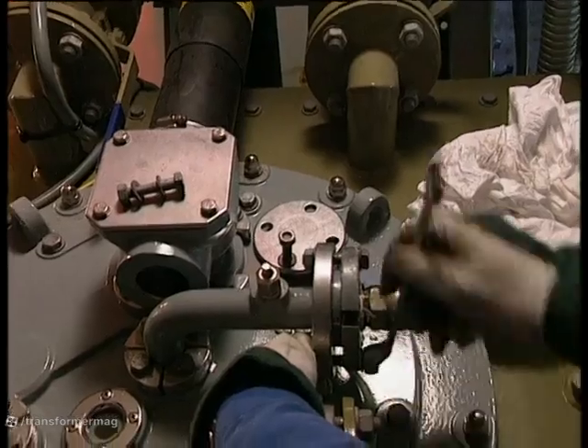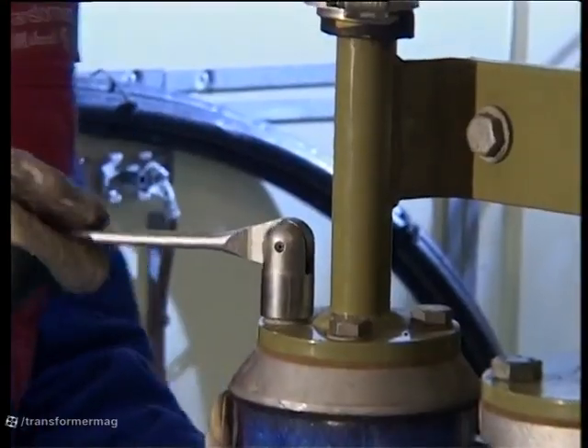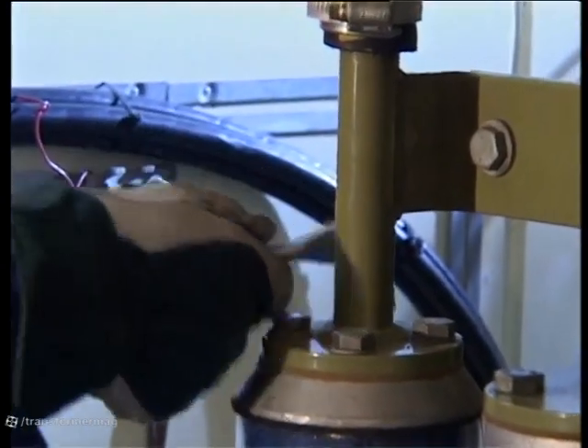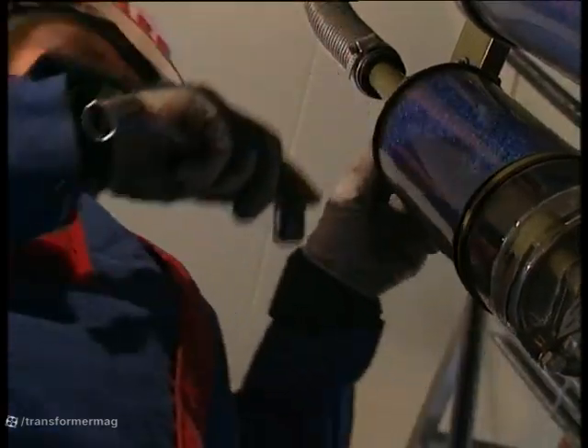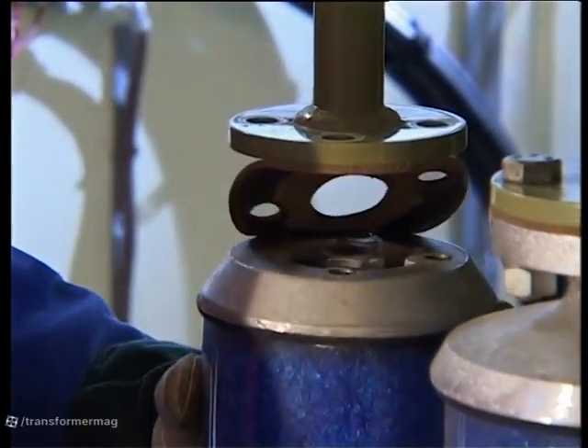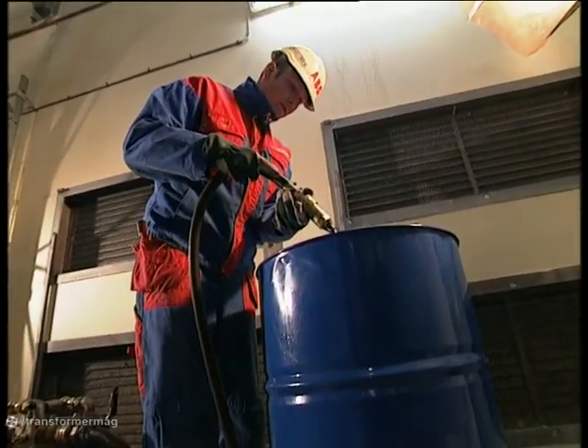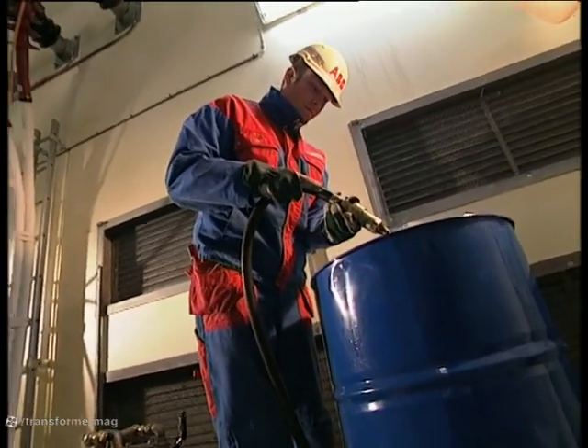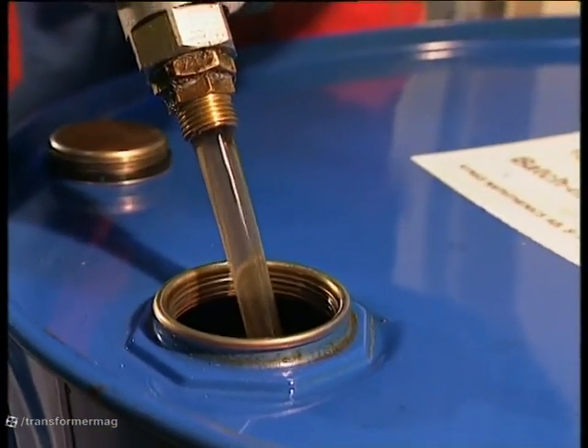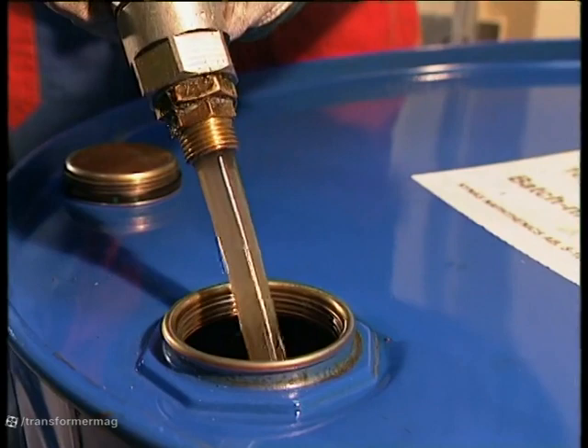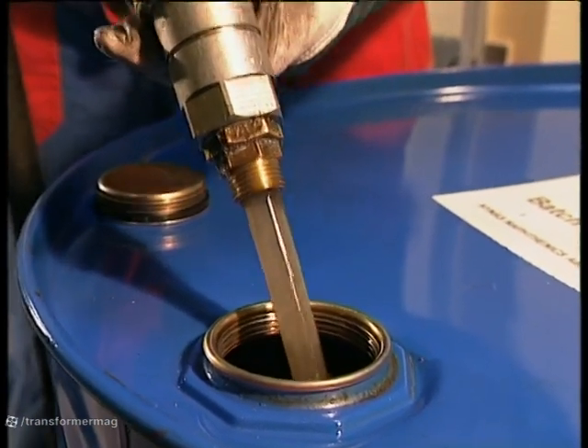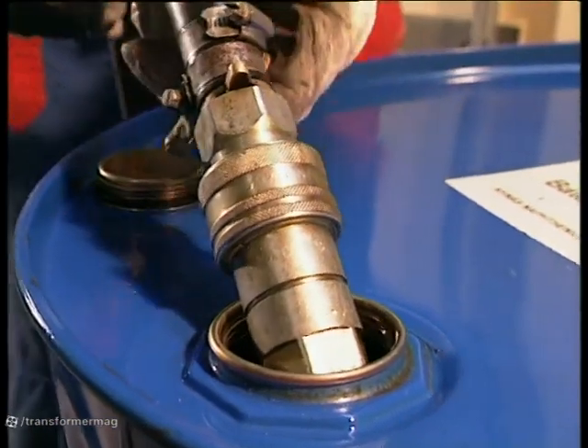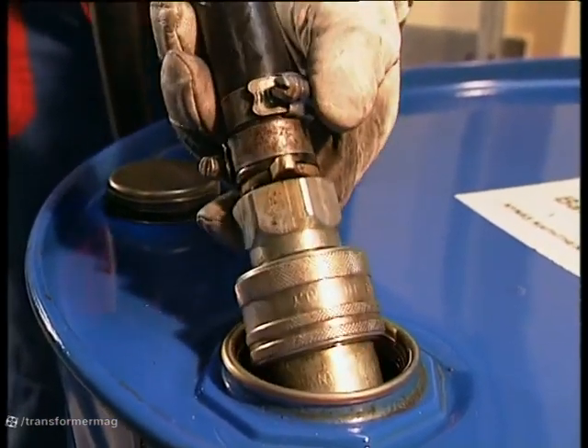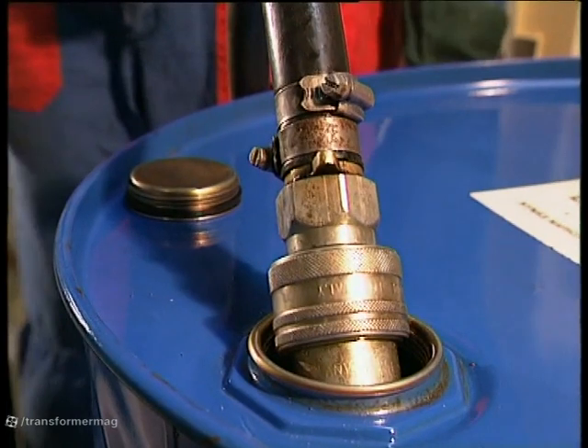Connect a hose and remove the dryer unit on the conservator. Open the valve in the pipe to the conservator. Pump out the oil. We also recommend flushing out the conservator and the tap changer, following the instructions in the maintenance guide. You'll have to remove more oil when the cover has been removed. We'll show you how to do this later.